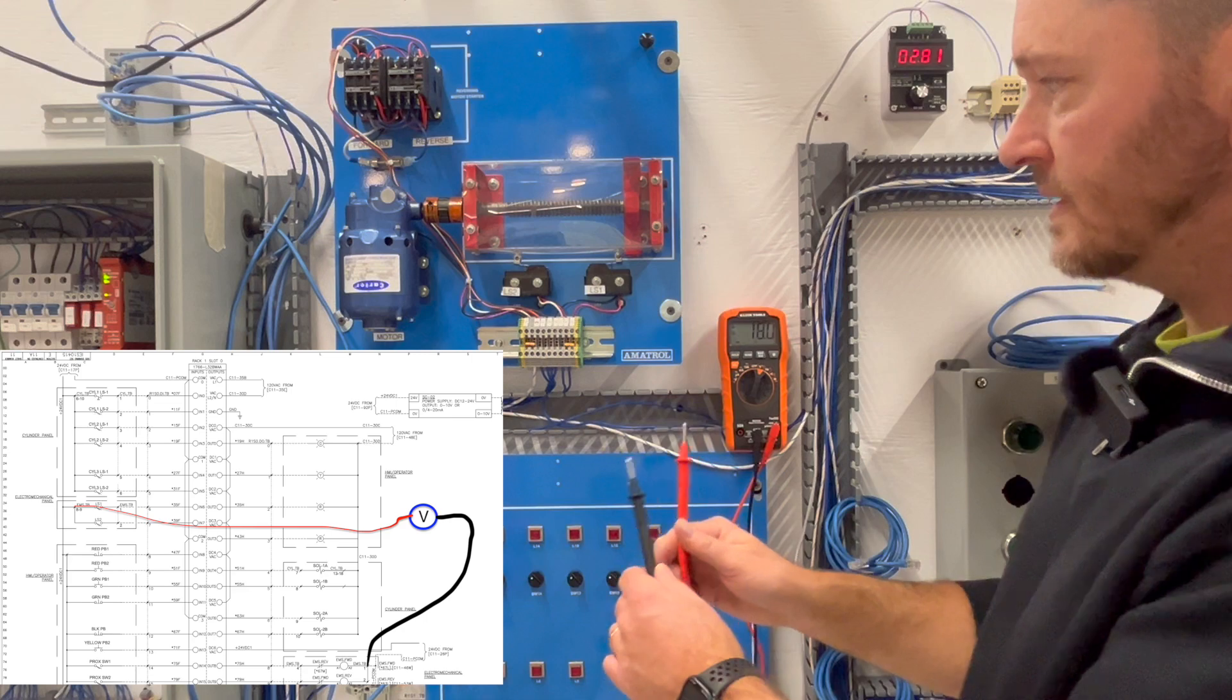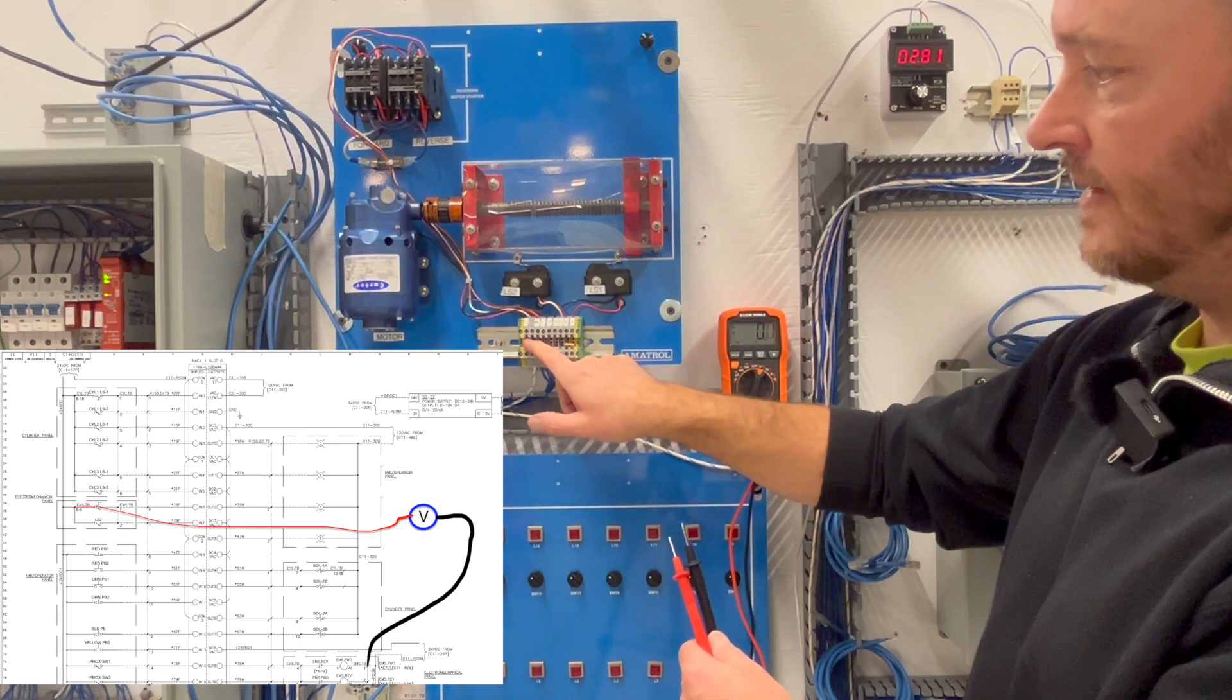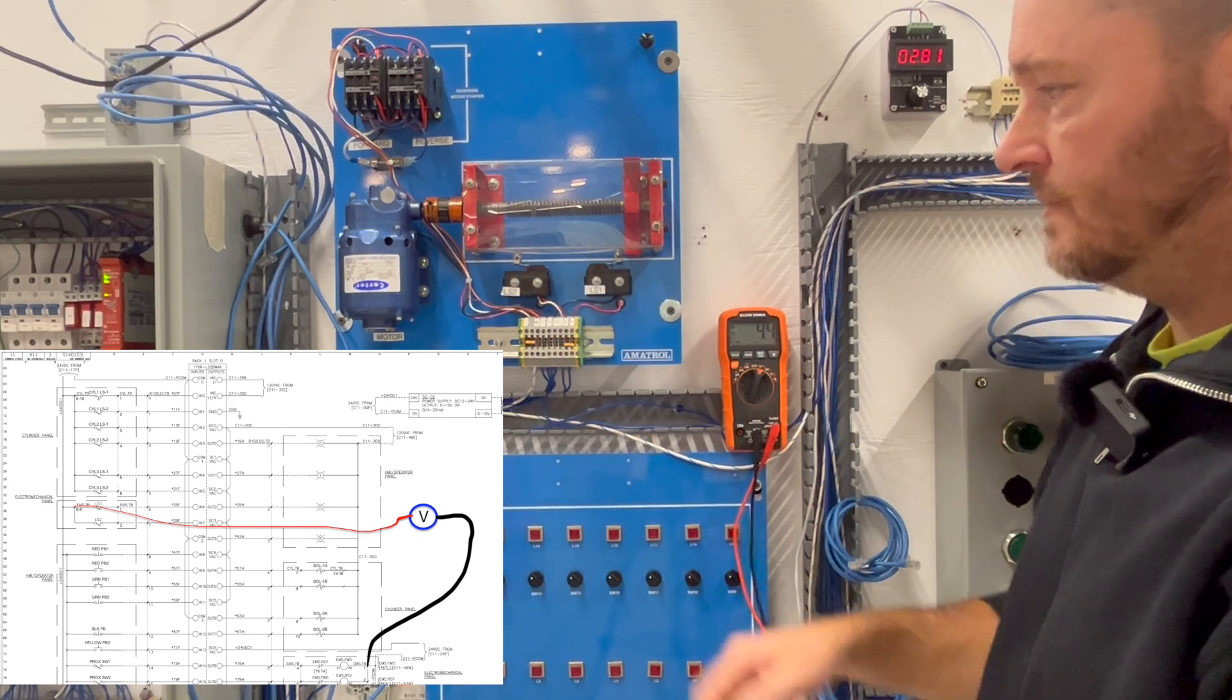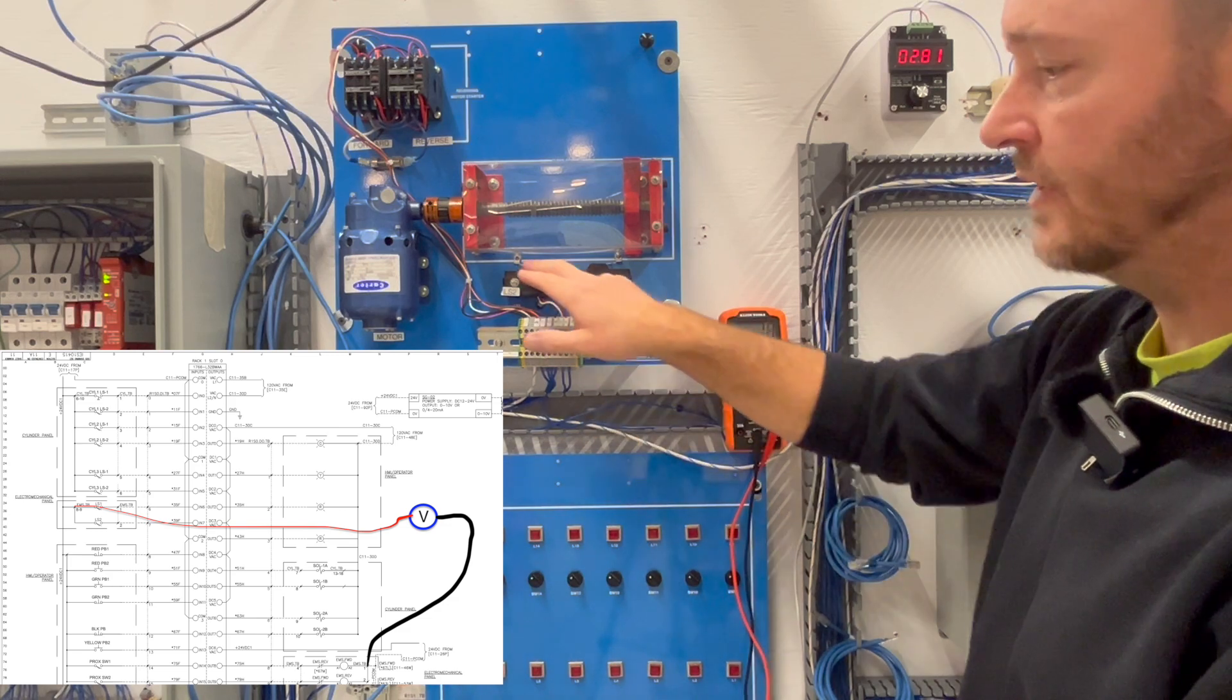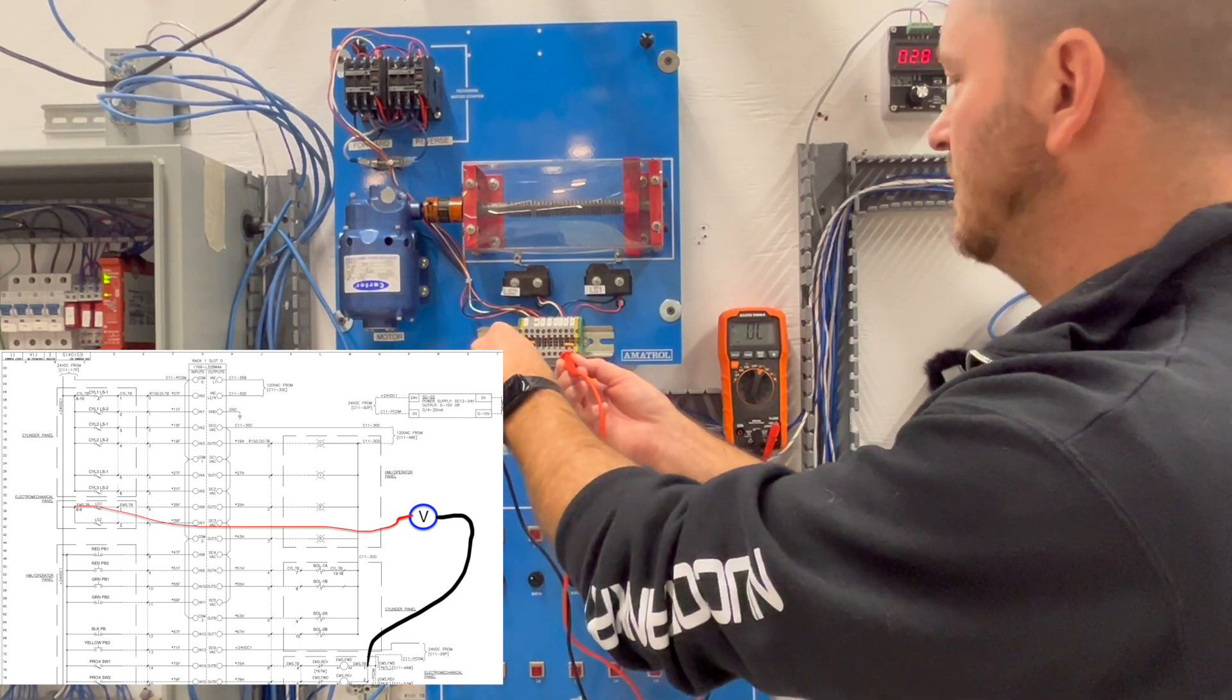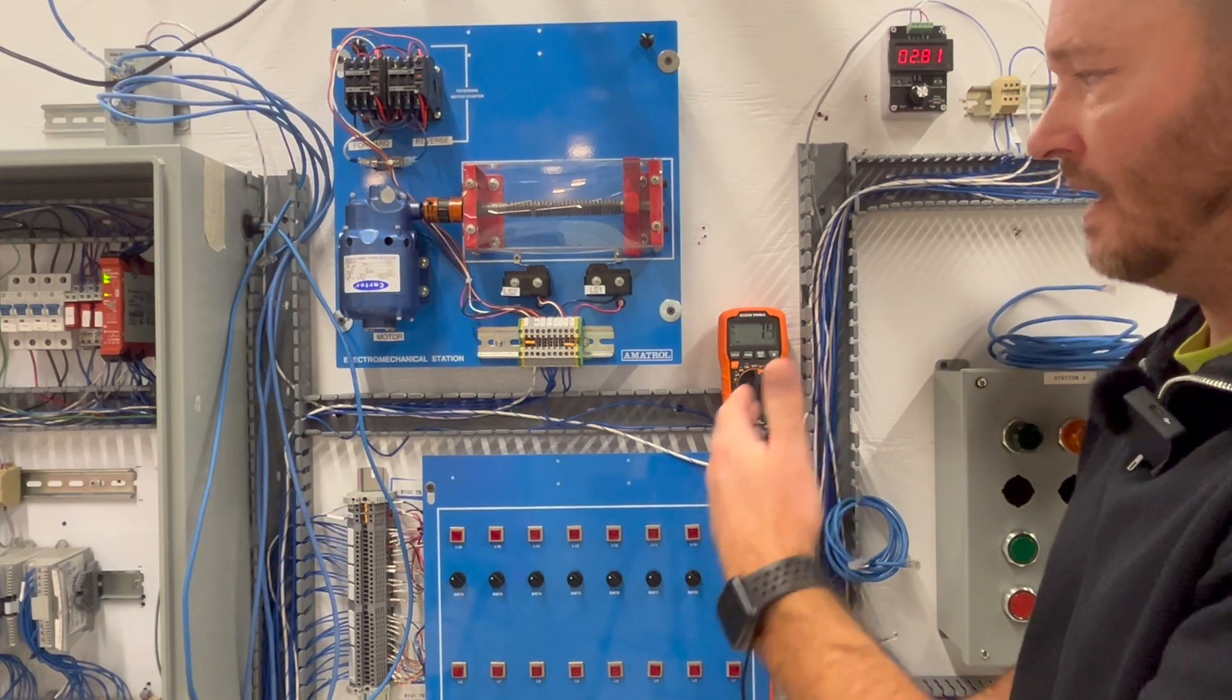The first thing I always like to do is to make sure that there is voltage to the terminal strip. This indicates to me that there is common coming into here and there's a jumper here that goes to the neutral on the output and there are two hotlines going to here. My instinct tells me that these are not the problems because if this was unplugged or didn't work or there wasn't 24 volts here my LS2 wouldn't activate. So I'm coming here and here and I am getting my 24 volts. So I'm good. So I know it's not a power supply problem or anything like that.